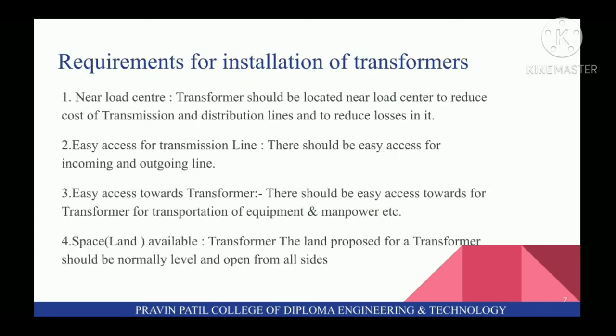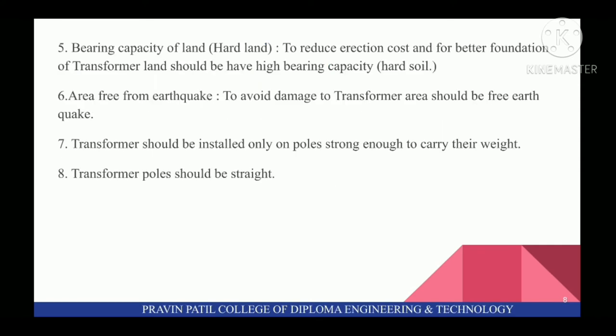Next is Requirements for Installation of Transformers. The first requirement is Near Load Centre. The Transformers should be located near Load Centre to reduce cost of transmission and distribution lines and to reduce losses. Second is Easy Access for Transmission Line — there should be Easy Access for Incoming and Outgoing Line. Third is Easy Access towards Transformers for Transportation of Equipment and Manpower. Fourth requirement is Space, i.e. Land Available — the land proposed for a Transformer should be normally level and open from all sides. Fifth is Bearing Capacity of Land, that is Hard Land — to reduce Erection Cost and for better foundation, Land should have High Bearing Capacity, i.e. Hard Soil.